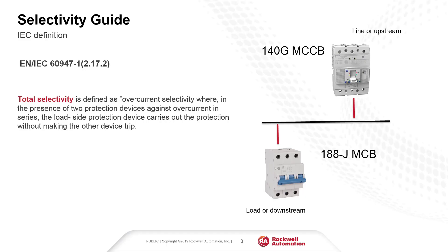As per IEC, Total Selectivity is defined as Overcurrent Selectivity where, in the presence of two protection devices against overcurrent in series, the load side protection device carries out the protection without making the upstream device trip.